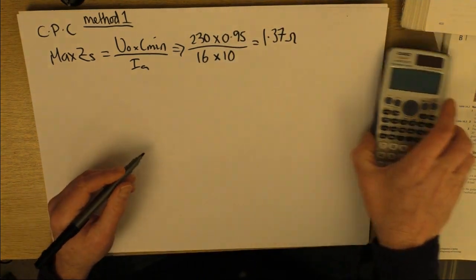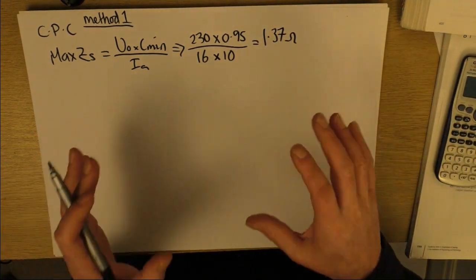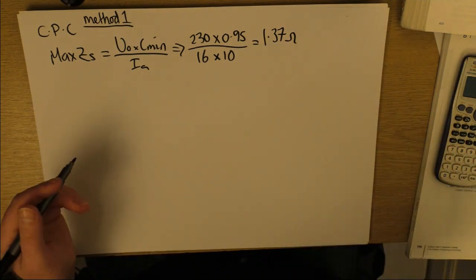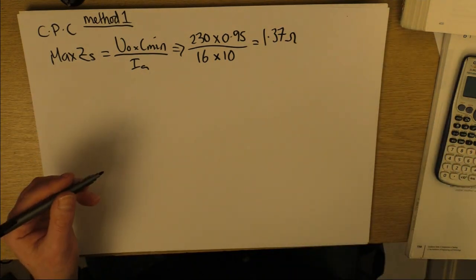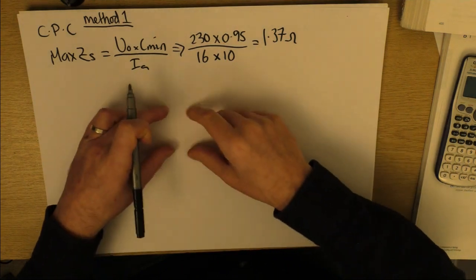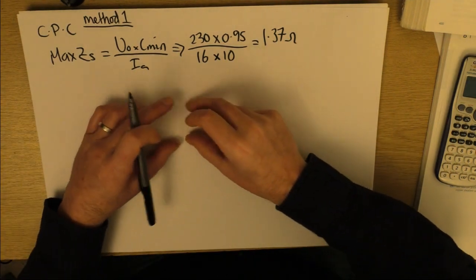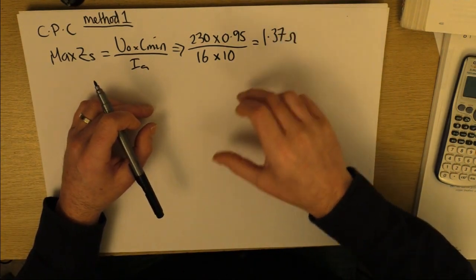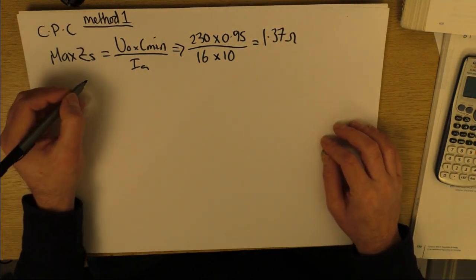Now that's at full temp, it's running, so it'll be at the limiting temperature, 70 degrees. So in a minute, we're going to need to calculate our R1+R2, but we need to get our R1+R2 up to that temperature, so we've got a fair comparison.